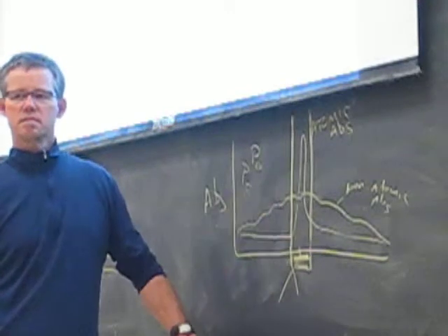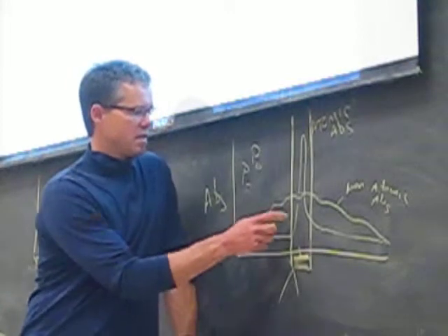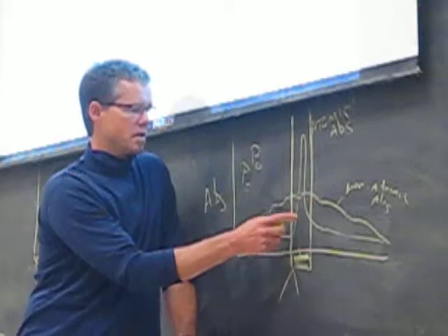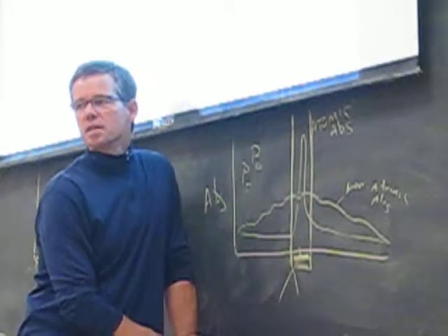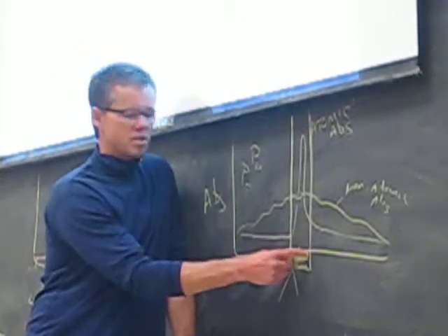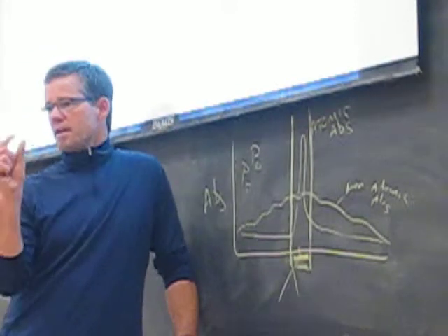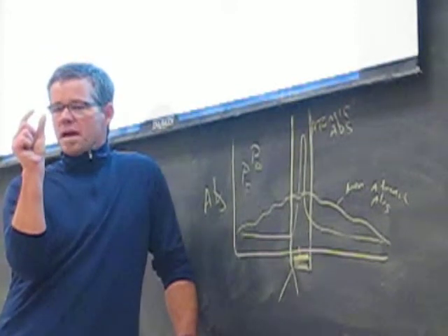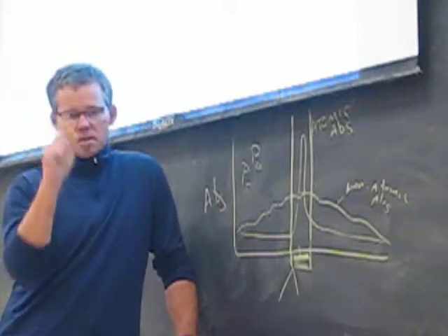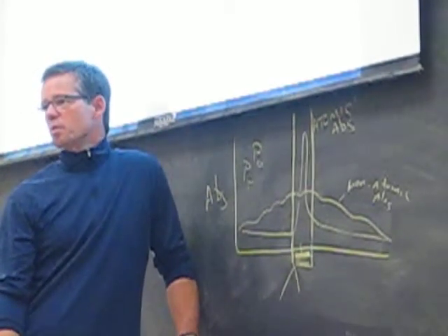Background, yeah. Well, if I could measure separately absorbance due to atomic absorbance and absorbance due to non-atomic absorbance, then I would get two different lines, right? Right. In your instrument, you can't do that. In your instrument, what you're measuring is total absorbance in this wavelength window. So you're selecting 324.8 nanometers, and the bandwidth of that absorbent peak is probably about 0.1 or 0.05 nanometers.